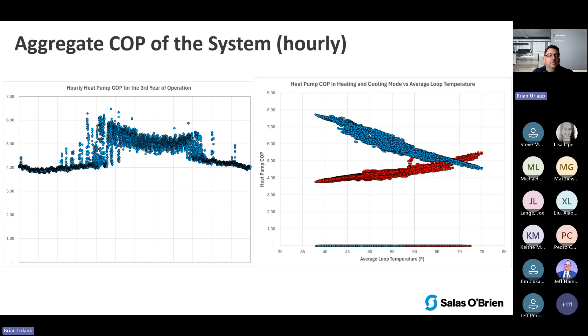So you look at the COPs of this system, you're seeing 4 to 6 and 4 to 5.5 COP in heating throughout the entire year. That would be the high point for a standalone system, not the average. We're seeing tremendous efficiencies and really good COPs across the year, not just seasonal averages but even at the worst times of the year, which I think is a good testament to why these systems can work and be very effective in providing efficient, low carbon solutions for the infrastructure we need to move to.